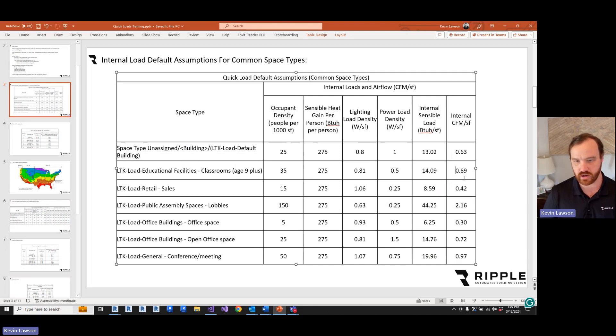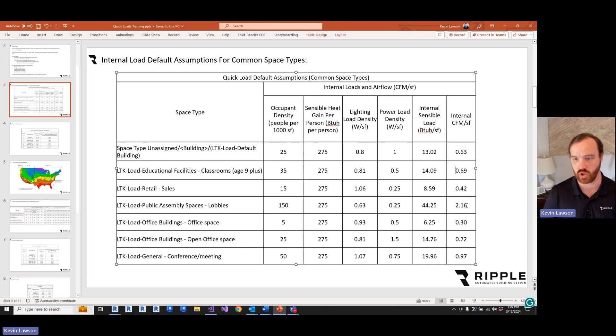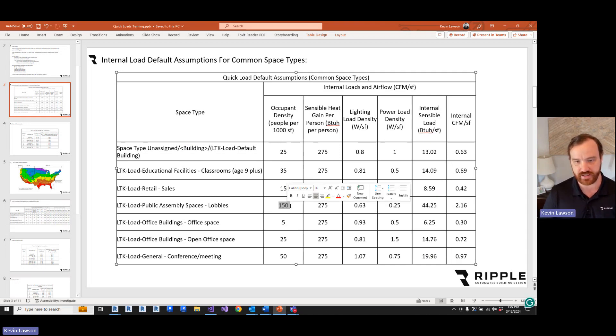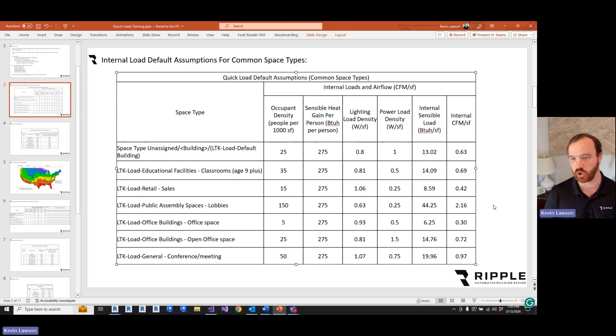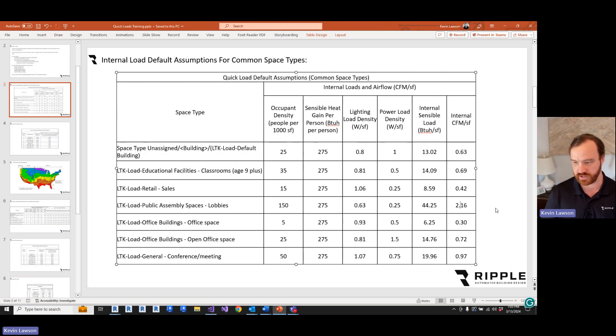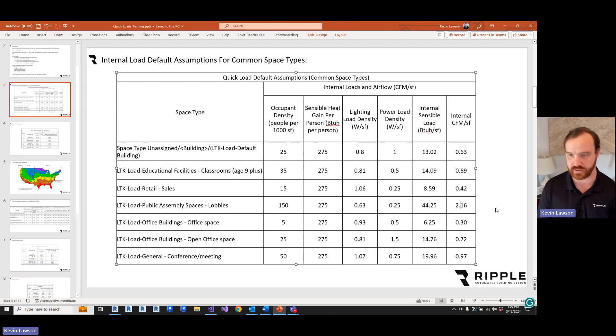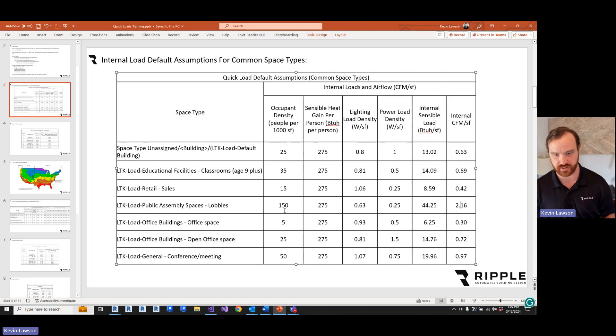And so here are some common space types and what the internal load is. Lobbies have 150 people per 1,000 square feet, so the default internal load for that is 2 CFM per square foot. That's why we're seeing the lobby at the highest airflow density in our project, because that assumption is made by ASHRAE 62.1.